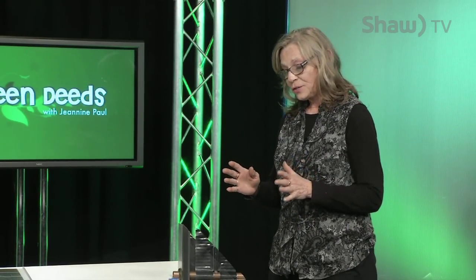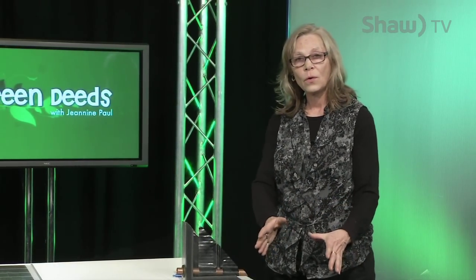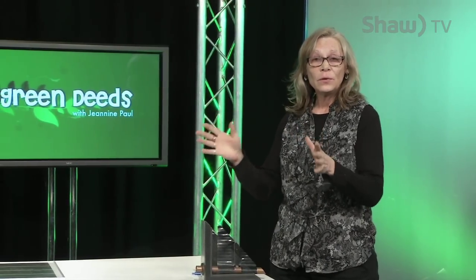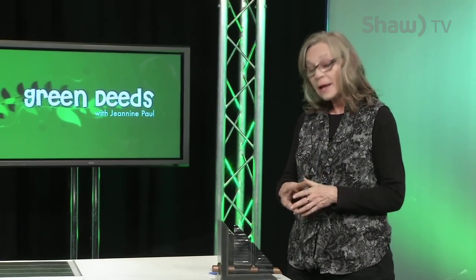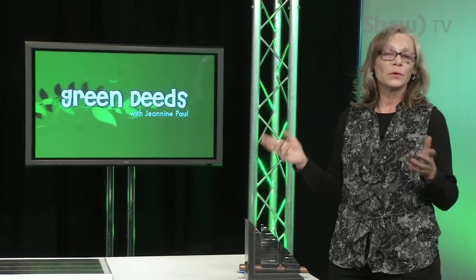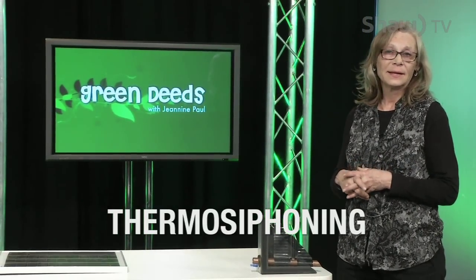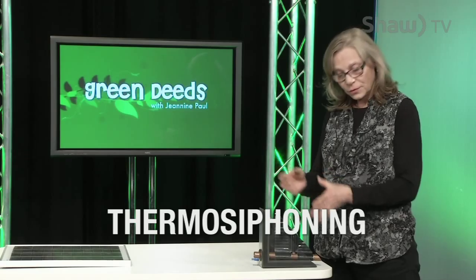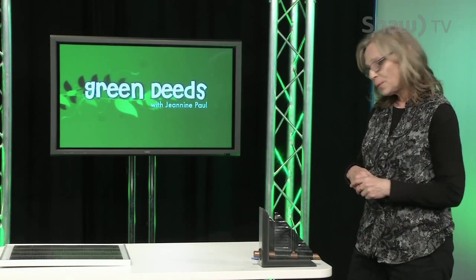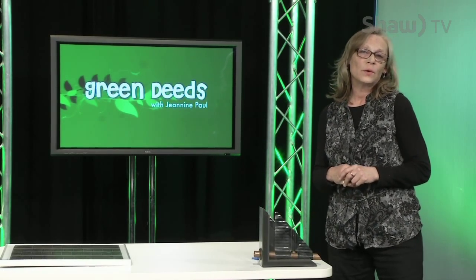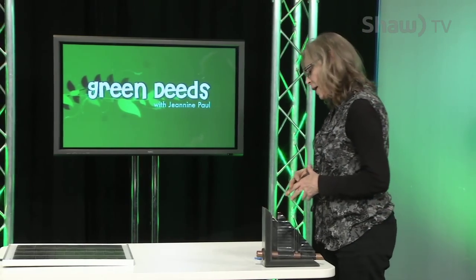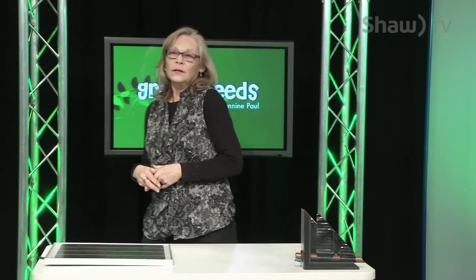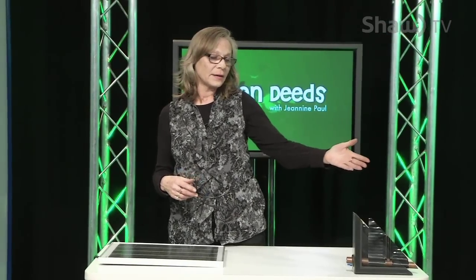If your panel is below and your tank is above, you don't even need a pump. The glycol will flow all by itself up through a process called thermosiphoning, and denser cold material will automatically replace it below. In most situations, where we put our panels on the roof or high to capture sun, you have to pump the glycol through the panel.